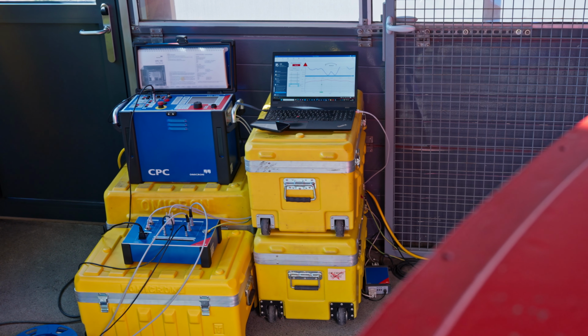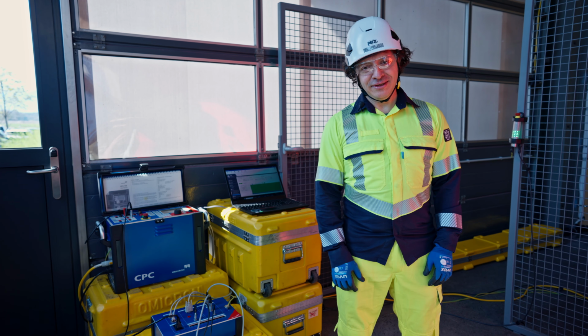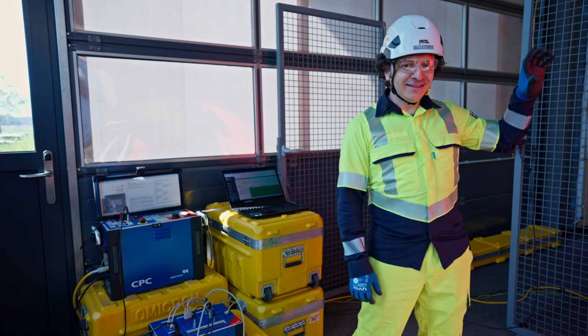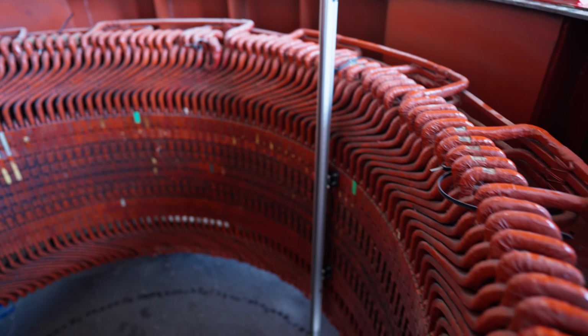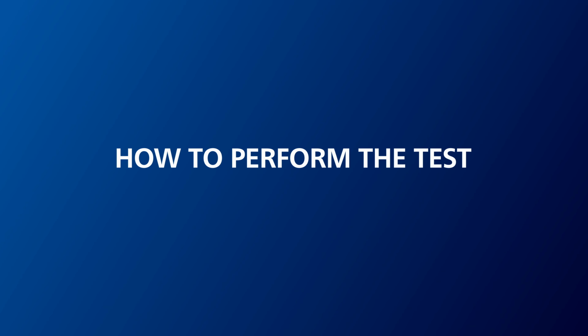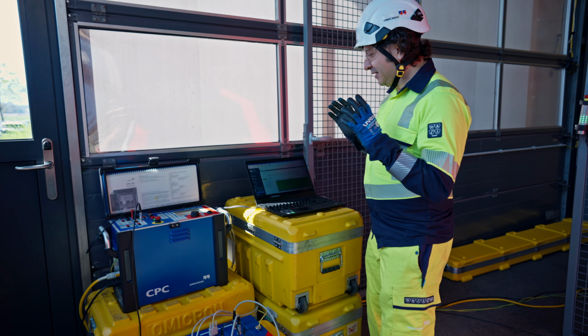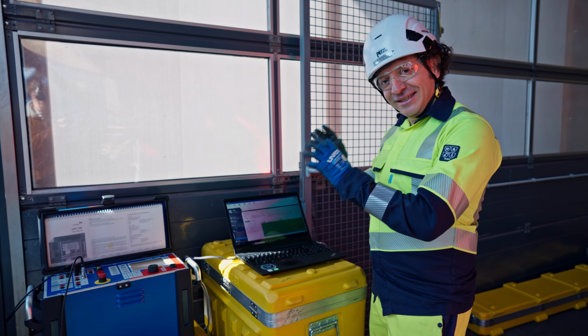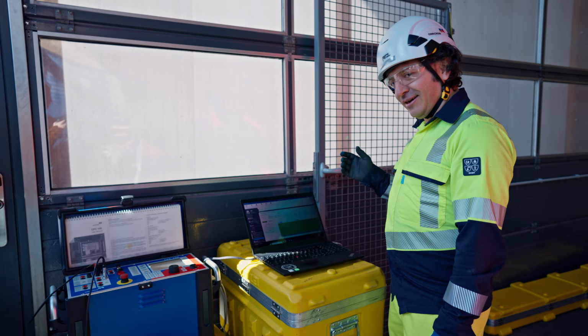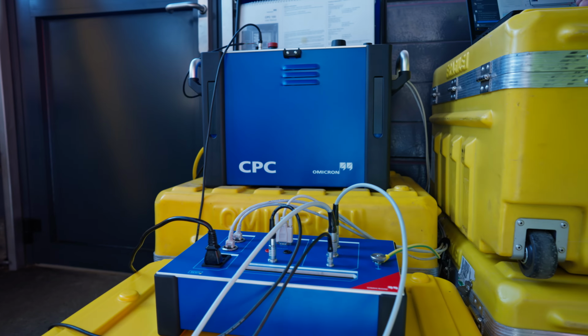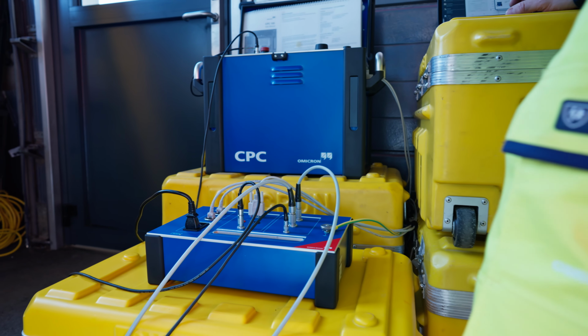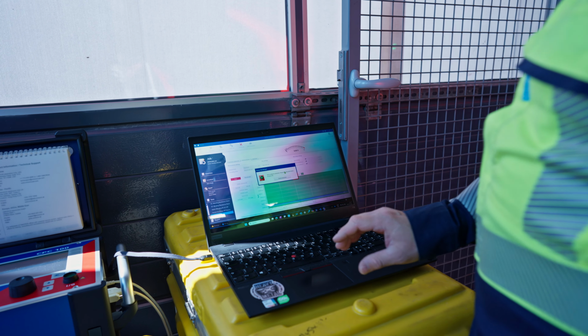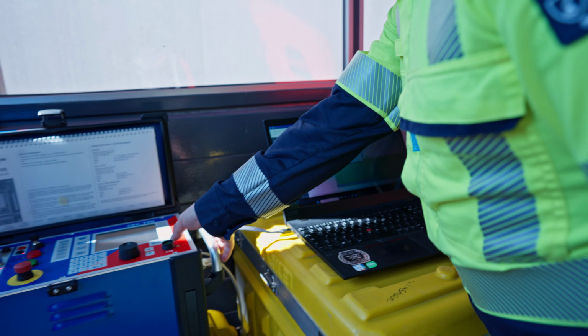I want to show you how to perform Stator Core Low Energy, or ELCID, measurements in this Stator Core that we have available for such purposes. For such measurement, we need to use the CPC 100 together with our well-known PTM software and the Stator Core Operate option. The measurement has to be performed in all the slots, so we are going to start with the first slot.